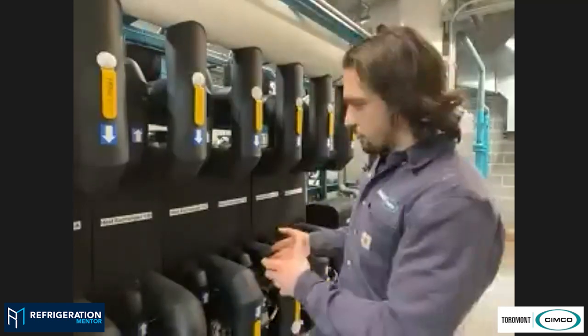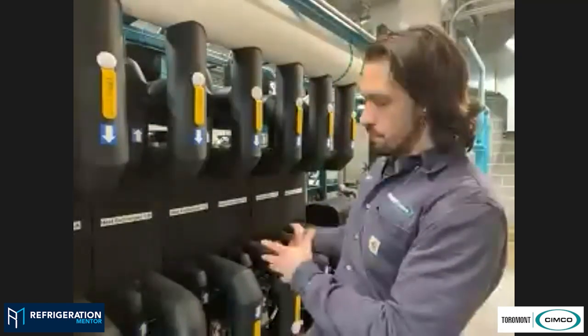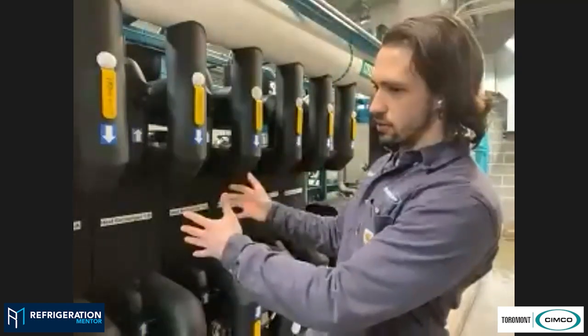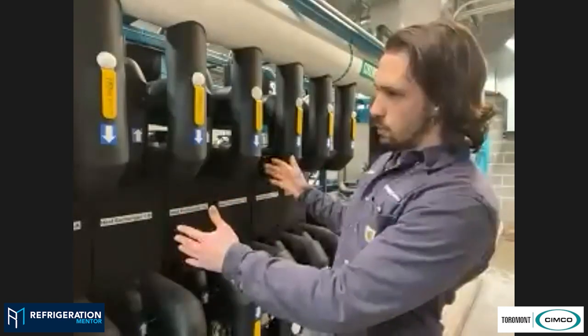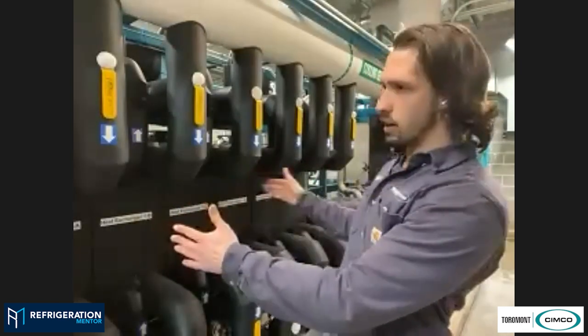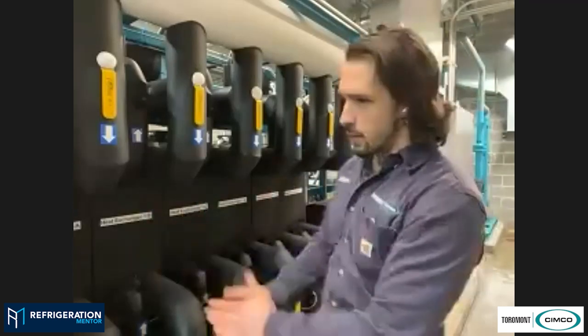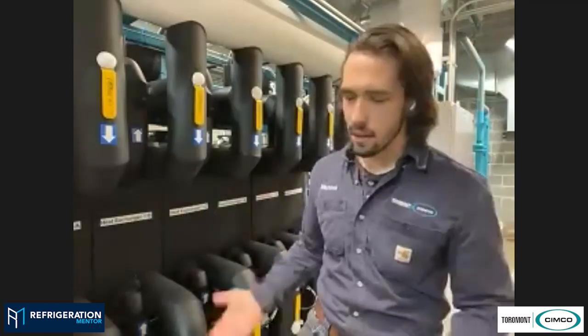So as we get closer with our hysteresis to our set point, we can start shedding back compressors, bringing compressors back on. But on a day like today where there's absolutely nothing going on in that rink, it'll turn on and shut off in a fairly short amount of time and stay off for a very long time.